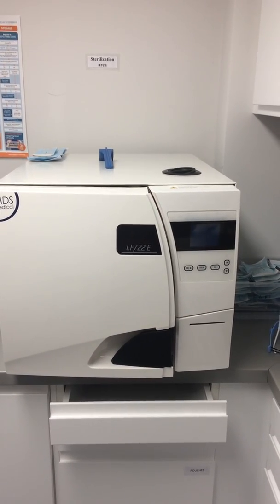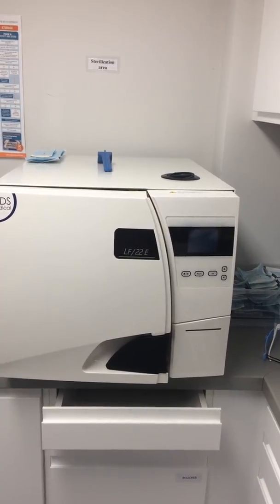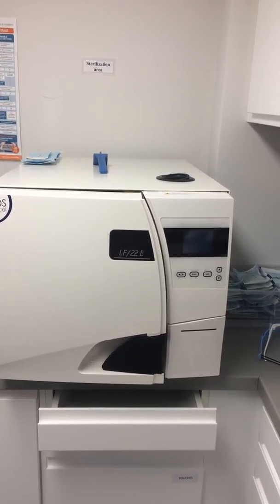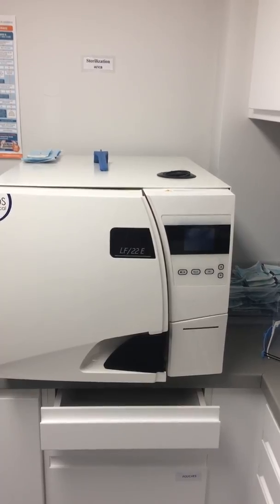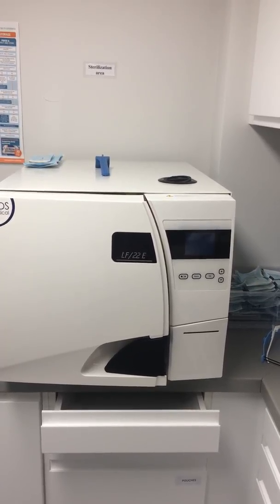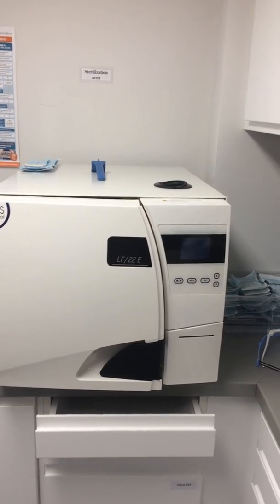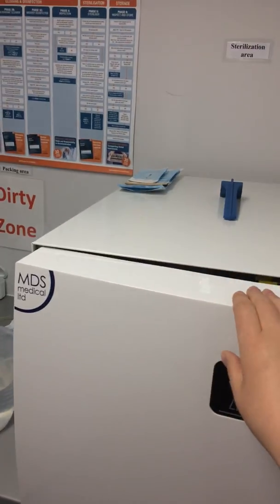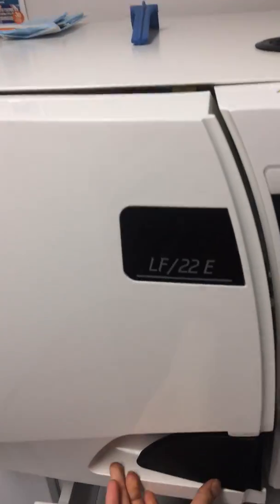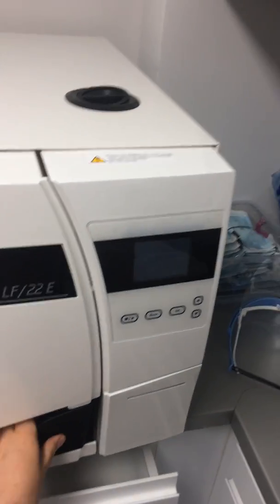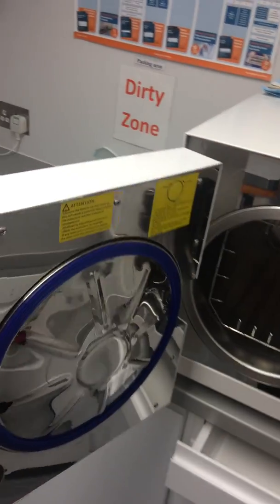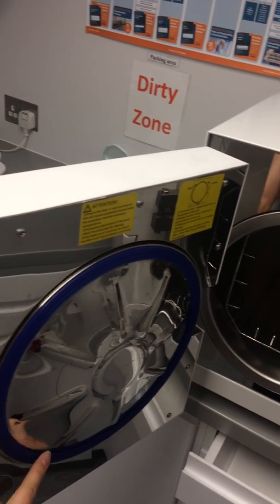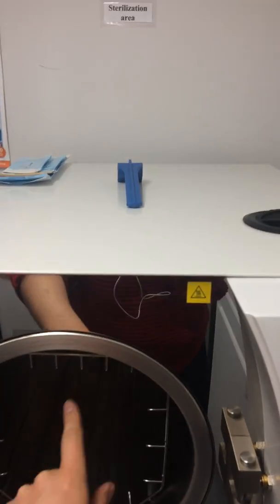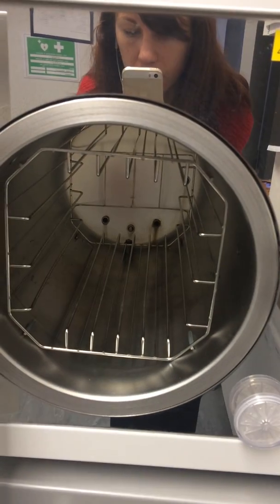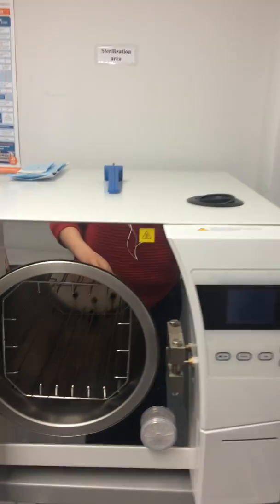How to operate it? In the morning before processing any instruments, the nurse has to clean the rubber door seal, check if the chamber is clean and fill the water tank with distilled or RO water up to the level. So how do we do it? We open the door. If it's closed, there is an interlock here, so we just push it and open. This is the rubber seal, which has to be cleaned with an alcohol wipe, as well as the inner chamber. As we can see, the nurse has done it the day before, so it looks clean.